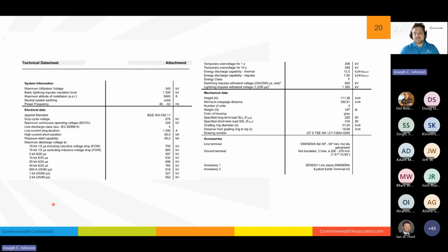So this is a data sheet. There's a lot of data here. I'm not going to go into all of it, but I just want to point out a few key things. This is a 345 kV arrestor with a 1300 kV BIL. Skipping over this real quick, we can see over here we have a lightning impulse withstand voltage with that previously called out waveform of both switching and lightning, actually. So this is the BIL, and the 850 is the BSL. We see some temporary overvoltage. It's not a graph, but it's a couple of points on the graph. Lots of mechanical data here, which we are not going to get into.